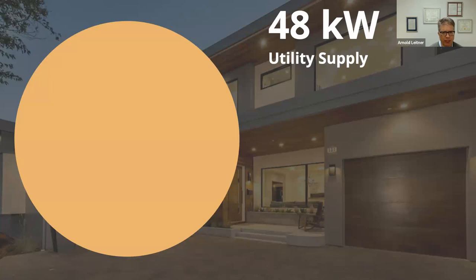But say you are on vacation, the home was warming up, you come home, and you have a central air conditioner, you push the thermostat to 72, and suddenly all the current rushes into these compressors. There's a very high current, we call it the inrush current, which results in very high power levels. You can snap up into the 30 or 40 kilowatt rating, despite the fact that the appliance itself is only rated continuously at some 10 or 15 kilowatts.